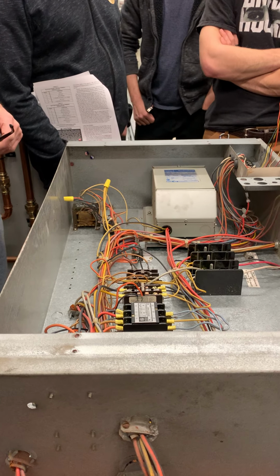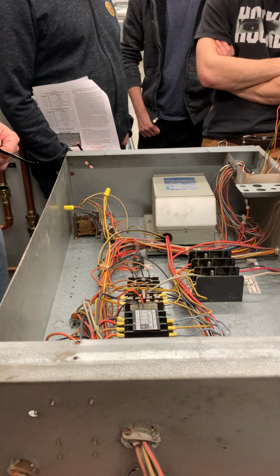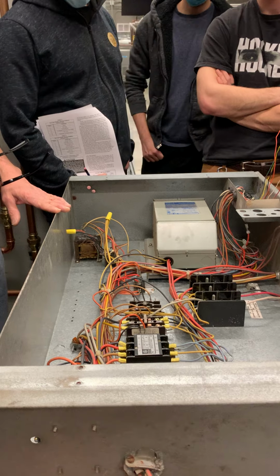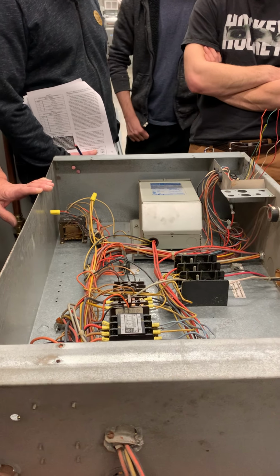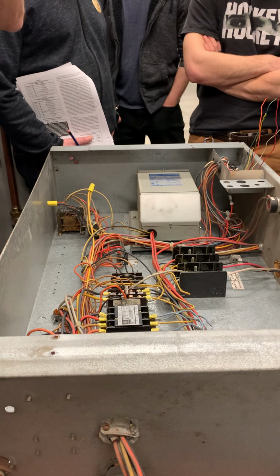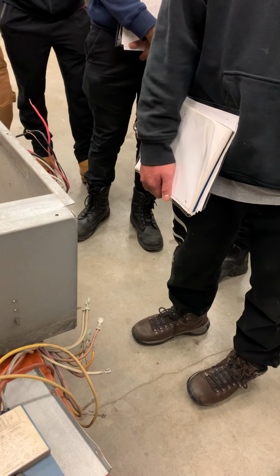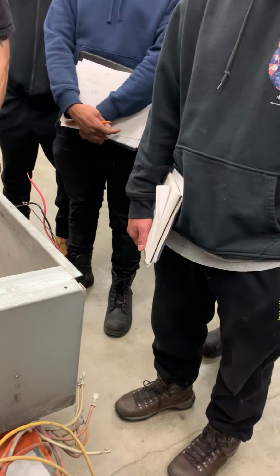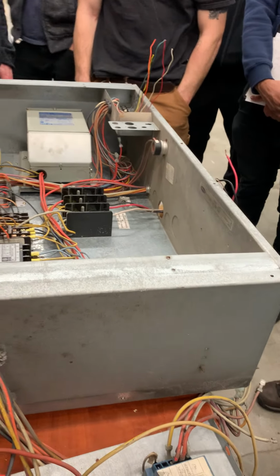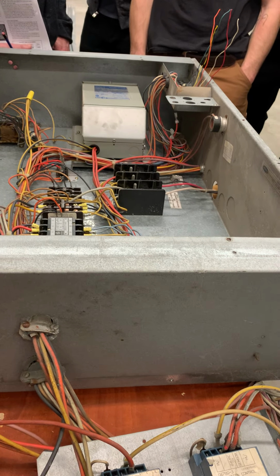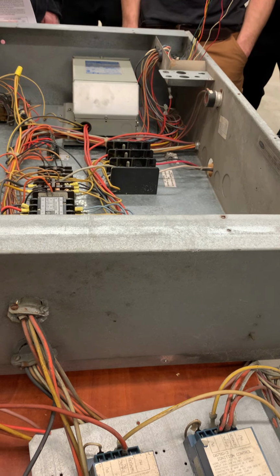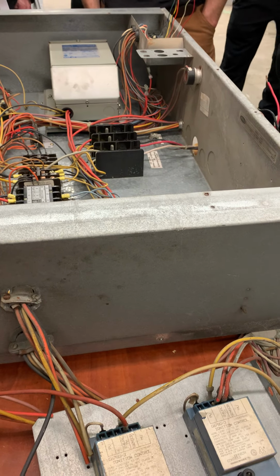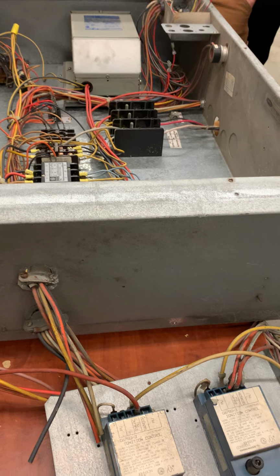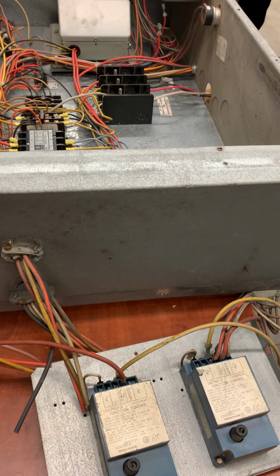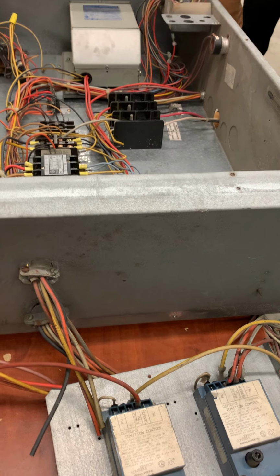460. Have you guys ever heard of 460 volts before? You know why? Because you live in Canada. If you lived in the US, you would know all about 460. What did I tell you we have in the large or the medium commercial buildings? 208. 3-phase 208, right? I told you the bigger commercial buildings will be 3-phase 600. In the US, on the medium commercial buildings, we're going to have 3-phase 230, not 208. And in the bigger commercial in the US, 3-phase 460. So in the US, they use 460 volts, where we use 600. They use 230, where we use the 208. So that's why they got the different voltage ratings on there.